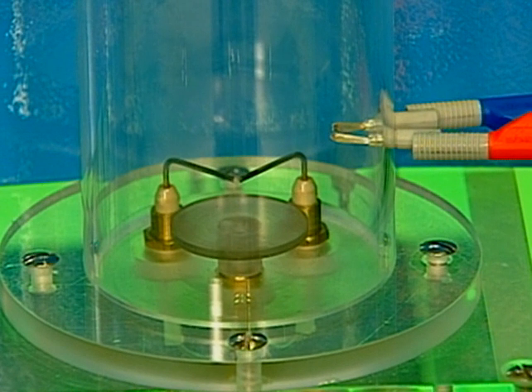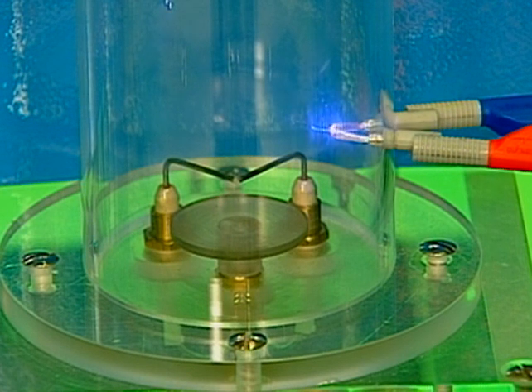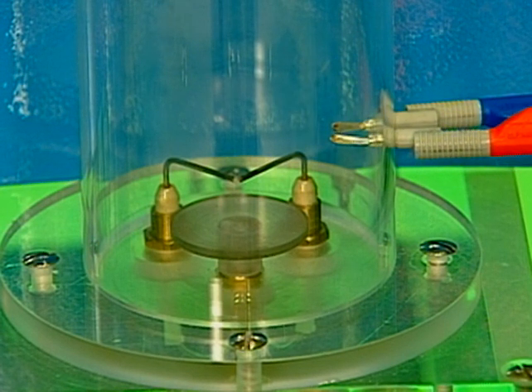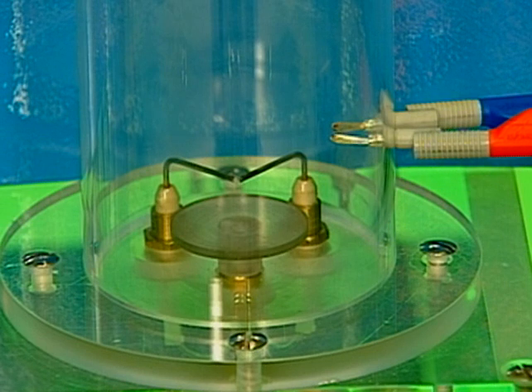We test the worst case once more, and short circuit the leads. A spark is created, is however unable to ignite the explosive air gas mixture. The ignition energy is too weak.